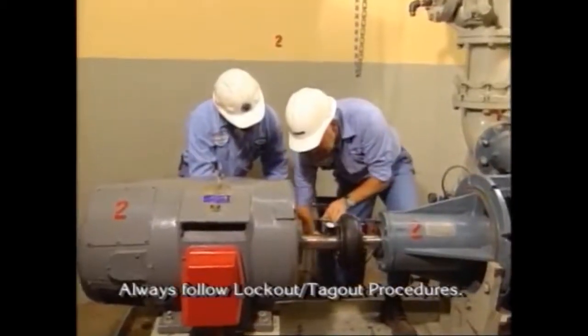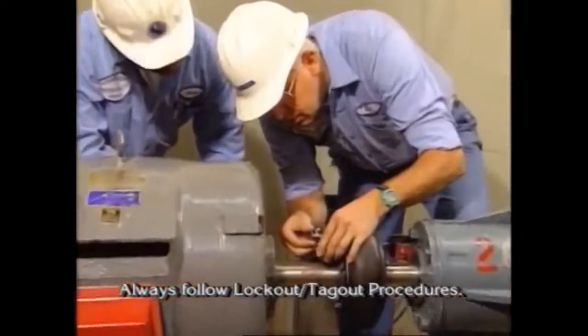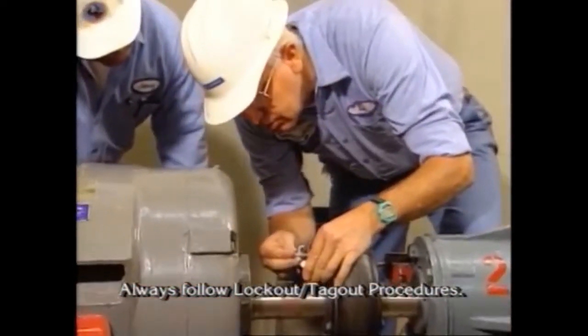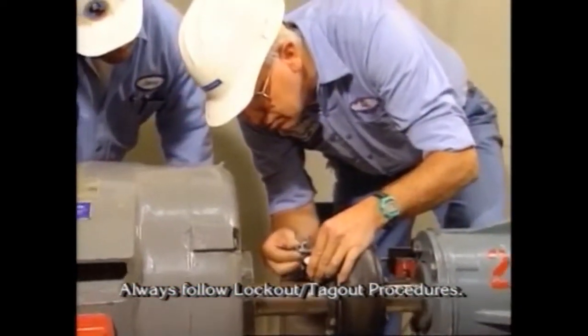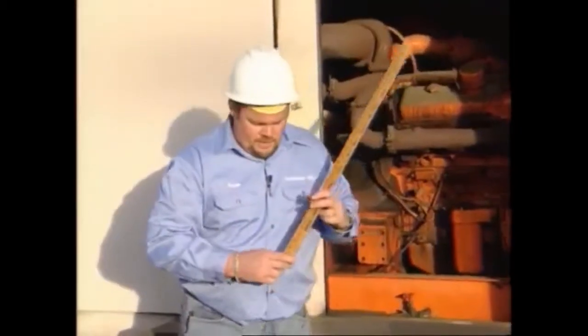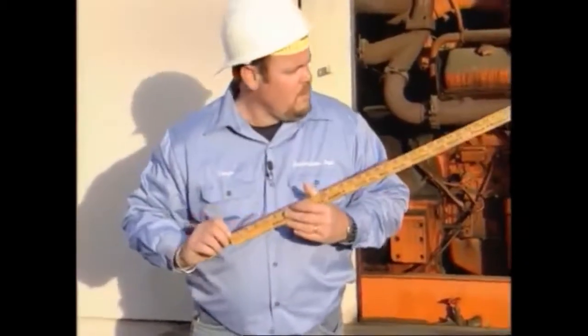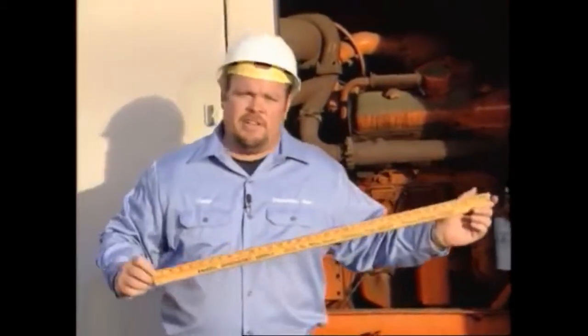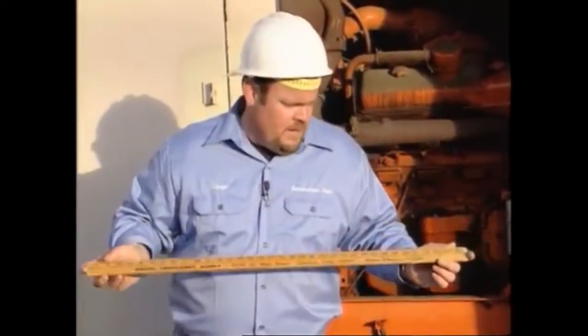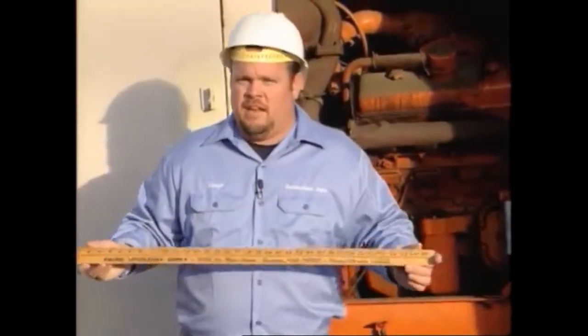The motor and pump shafts must be aligned to within manufacturer specifications for the particular coupling, usually within plus or minus 1/100th of an inch. Let's see, that's well, this one only goes to 35, so it'd be like three of these. I didn't know there'd be math.